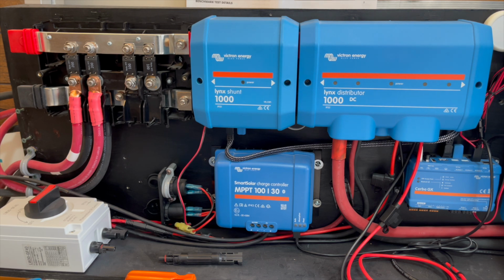This system over the summer proved to work really well, and I'm very pleased with it. I designed it - it's about a 15-inch by 48-inch frame support, self-supporting. I slide it underneath and I can slide it out. The only thing I need to disconnect is the batteries and hook them up. There's enough room behind it to fit all four of the SOK 300Ah units. I'll have a capacity of 1200, and that's more than enough.